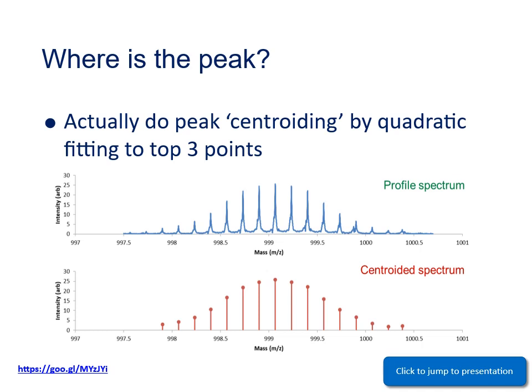The benefit of the centroided spectrum is that you can see a quick summary of the peak positions in a spectrum. However, the dis-benefit is you've lost all the information about the shape of the peaks, any potential shoulders on the sides of the peaks, and you can no longer see the noise, so it's hard to get an idea of the quality of the spectrum. As an expert mass spec user you'll come to miss that missing data, and start to appreciate the extra information that's held in the profile spectrum.